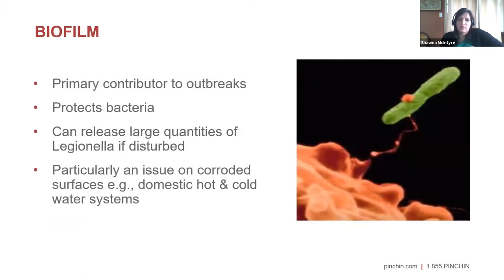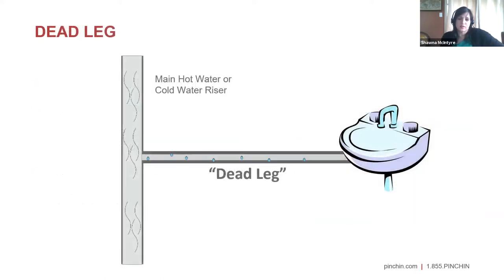Another thing that helps the bacteria grow within our water systems, within our buildings, is biofilm. They are a huge contributor to outbreaks within buildings. The biofilm is like a thick, slimy coating that can line the inside of our distribution pipes, and it acts as a protection barrier for the bacteria. They can grow and live inside this biofilm, and the water going through the pipes is not going to disturb it. However, large quantities of the bacteria can be released and disturbed all at once, especially if there's a source that causes a pressure differential, such as turning off the water supply system, conducting repairs, and then restarting it again. This is particularly an issue on corroded surfaces, especially within our domestic hot and cold water systems.